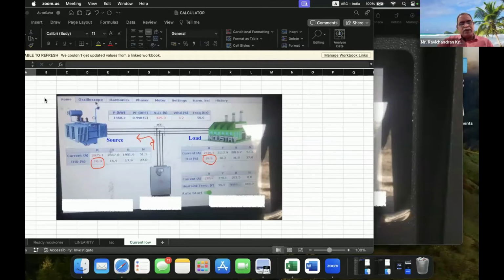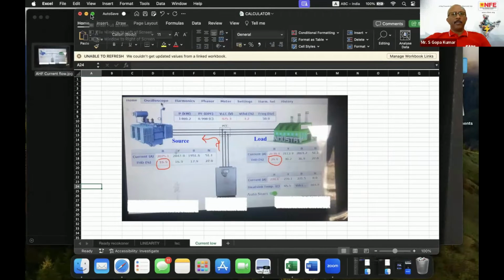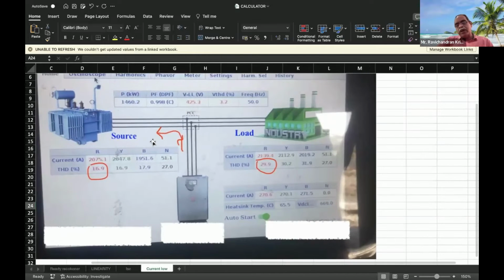And the active filter is an off-the-shelf available solution, but as Dr. Chilikuri said, it creates the supraharmonic, and we never addressed this issue. Secondly, since the active filter is installed at the LV side of the distribution system, and the harmonic frequency that it injects is the negative sequence harmonic frequency, that will enter into the source only. So if you consider the load side, the harmonic distortion is the same as before the filtering; there will be no change. So the purpose of the active filter is the compliance requirement. If you want real mitigation, the active filter is not going to solve your issue. And also this is proven by the readings. So unless it is installed at the load end, the active filter is not going to solve the issue. But installing at the load end is expensive.